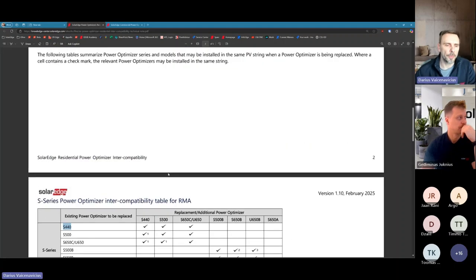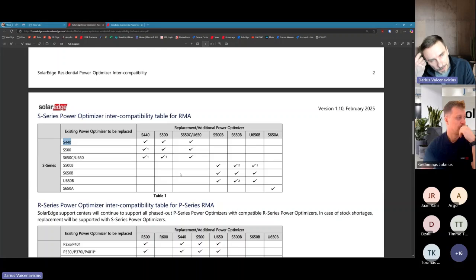So why is that? Because, for example, when the inverter and the string are operating, it depends on the available power or irradiance. So basically, the system decides how much voltage the optimizers should output to keep, let's say, the maximum available power.